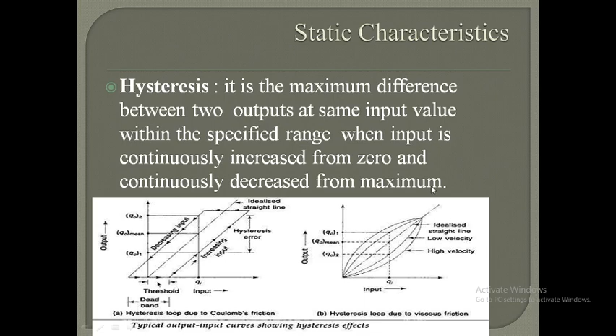So the change in the output from its original output shows the hysteresis error. Okay, because we are not receiving the same output again that we received when we were increasing the input. So that change in output from its original position is the hysteresis error. That shows the hysteresis error of the measuring instrument. So at the same input value we are getting two outputs. The difference between two outputs at the same input within the specified range, when input is continuously increased from 0 and continuously decreased from maximum, is the hysteresis.